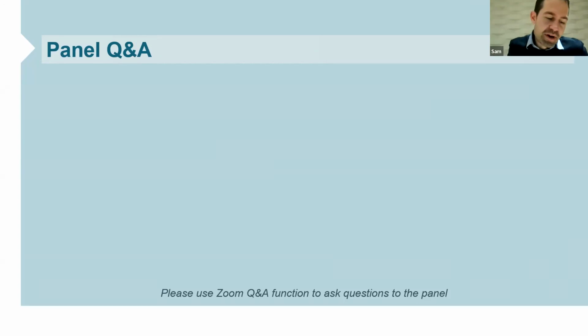I might chip in there. We've looked at this specifically for the Darlington Point BESS and done some studies on it. It depends on what you're trying to achieve. For frequency response, you obviously need active power and headroom. But what we've found is if you're just trying to stabilize oscillations, the active power element of the response isn't critical. We've shown that regardless of the starting state, even with the battery operating at full output, you're still able to have that dampening impact on oscillations.